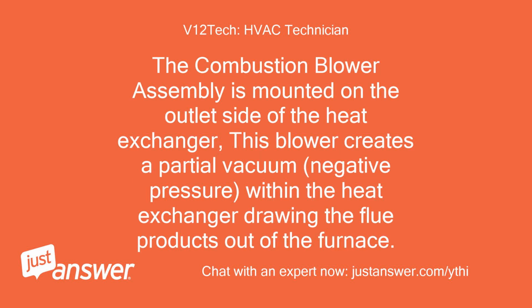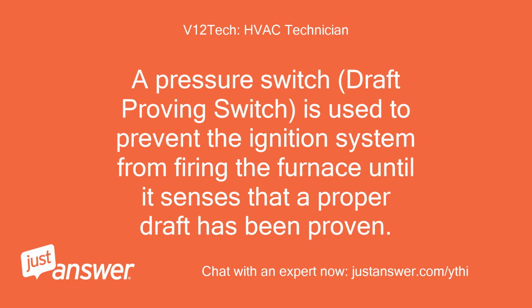The combustion blower assembly is mounted on the outlet side of the heat exchanger. This blower creates a partial vacuum, negative pressure, within the heat exchanger, drawing the flue products out of the furnace. A pressure switch, draft-proving switch, is used to prevent the ignition system from firing the furnace until it senses that a proper draft has been proven.